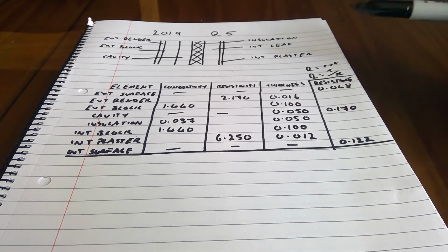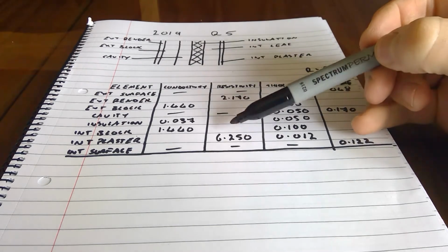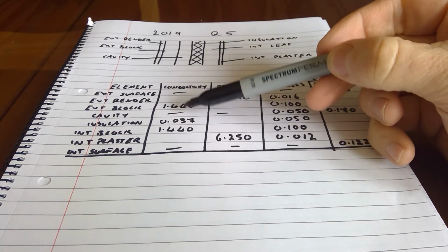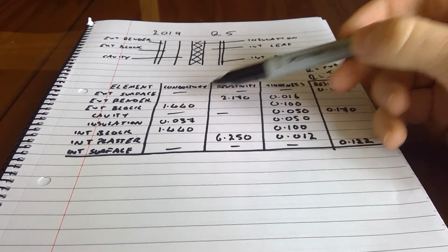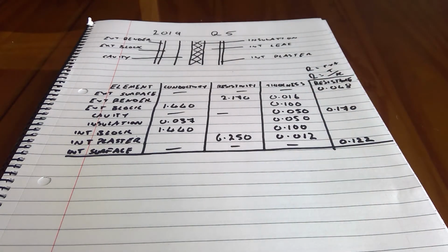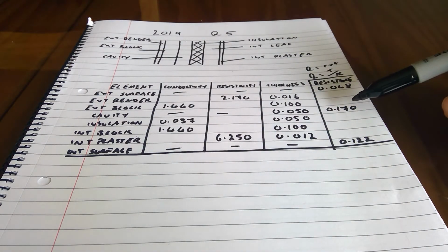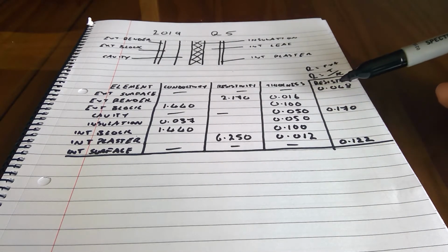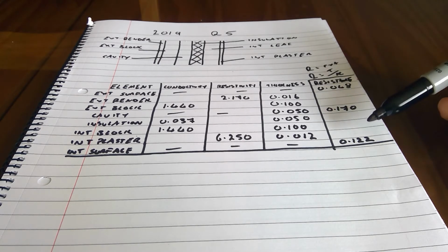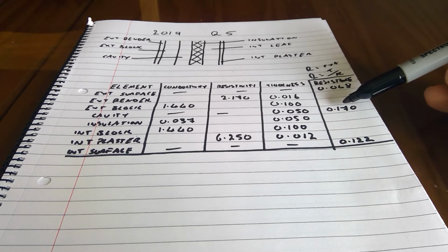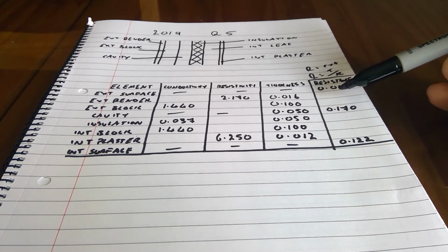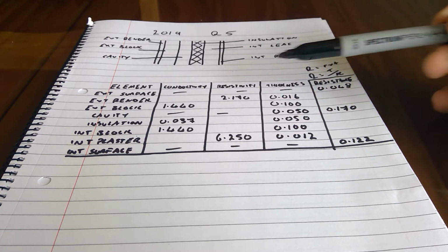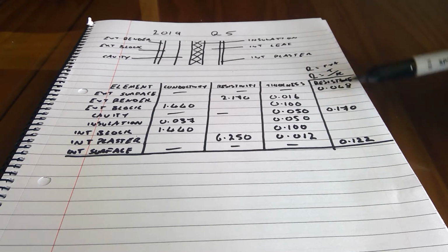Also, something to watch out for, in some situations they gave resistivity, in some situations they gave conductivity. Make sure you put these things in the right columns. Now, at that point then, as we all know at this stage, we just have to find our resistance. It's always all about finding resistance. For the external surface and the internal surface, they gave us resistance, but also for the cavity, they gave us the resistance. The cavity is just air, so things that you can't really calculate thickness for. I know there's 50mm for the cavity, but it's air you're dealing with. They usually just give you the full resistance. So we have full resistance for those. We need to calculate this, this, this, this, and this.